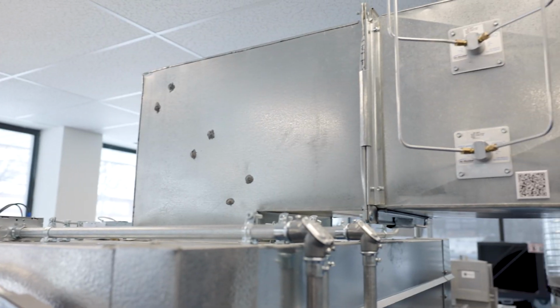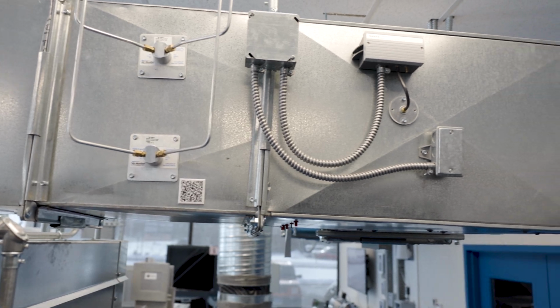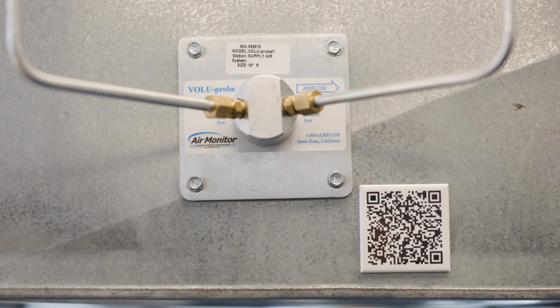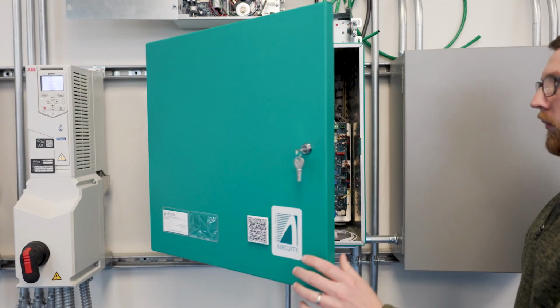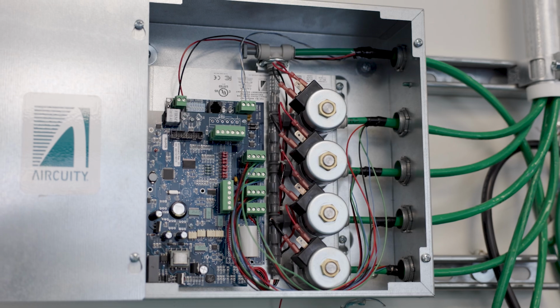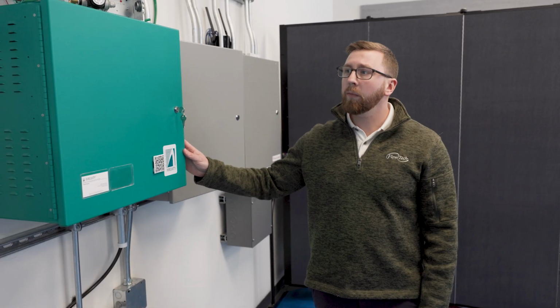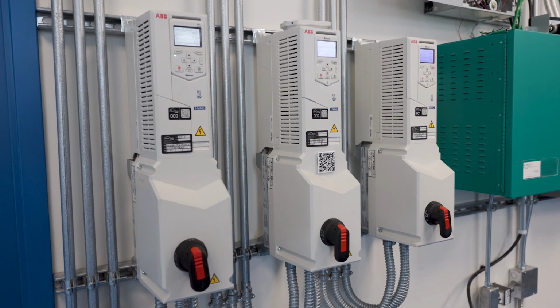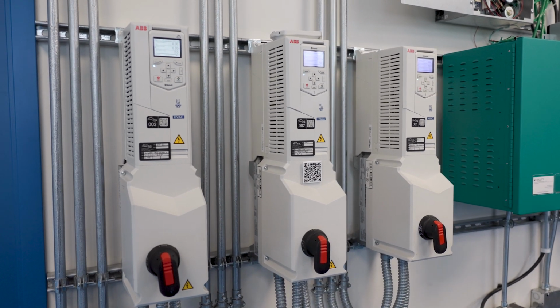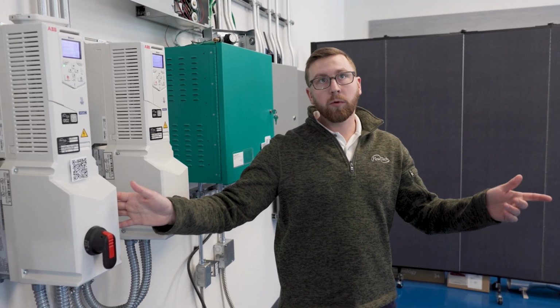Following the air path down, the air comes through the fans, through our supply ductwork, passing through a couple of pitot tube style air monitor airflow stations. So that actually measures the airflow going through the duct. We have a fully working DCV Aircuity system that tells our BMS system whether to increase or decrease airflow. We have a couple VFDs on the wall. One is for the Twin City supply fan inside the unit. The other 2 are for our lab exhaust fans, which we'll get to shortly.